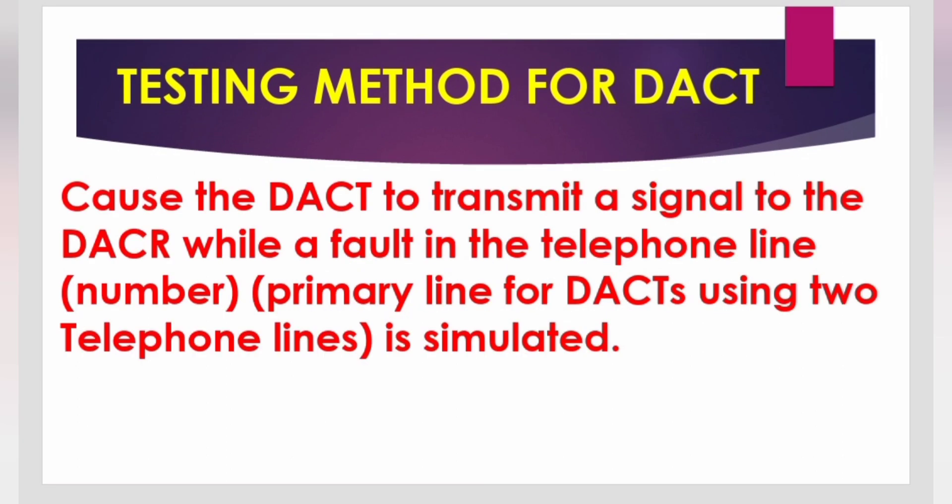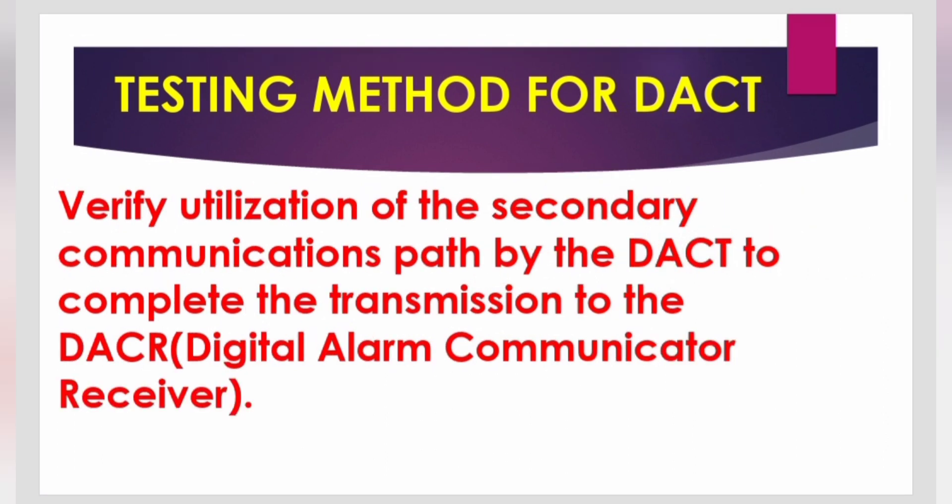When considering the digital alarm communicator receiver factor, cause the digital alarm communicator transmitter to transmit a signal to the digital alarm communicator receiver while a fault in the telephone line primary for digital alarm communicator transmitters using two telephone lines is simulated. Verify utilization of the secondary communications path by the digital alarm communicator transmitter.